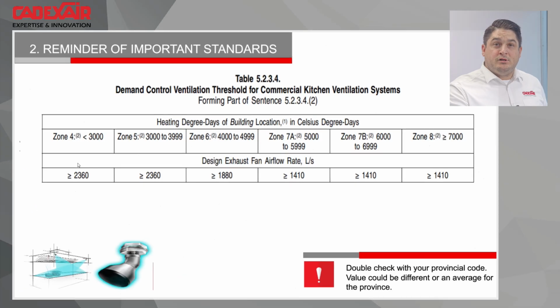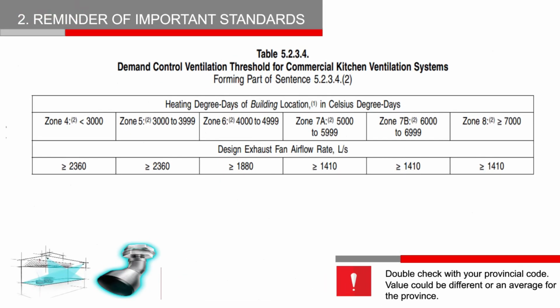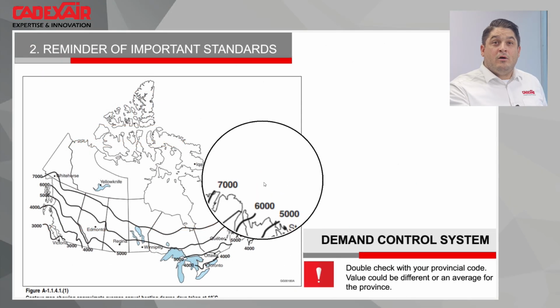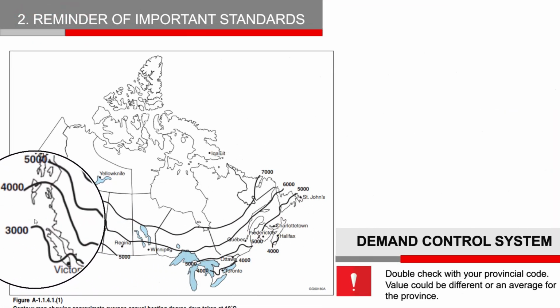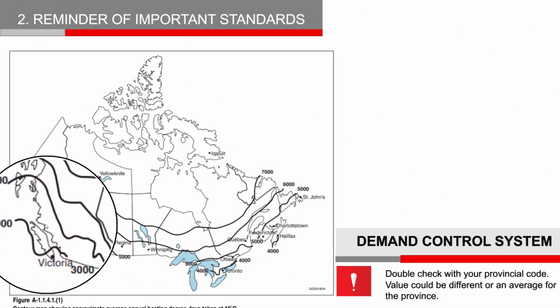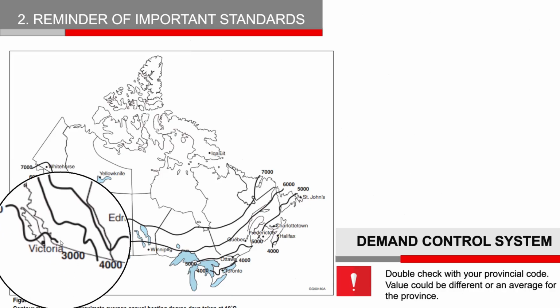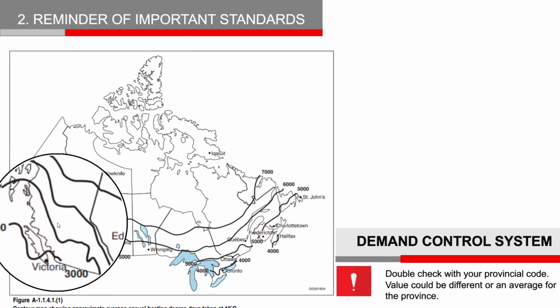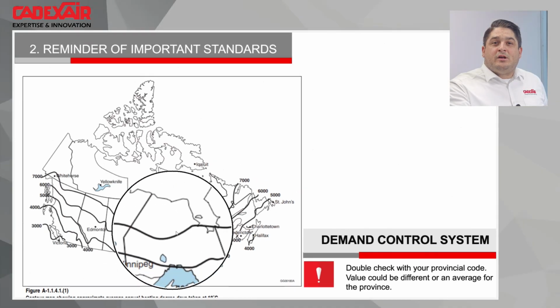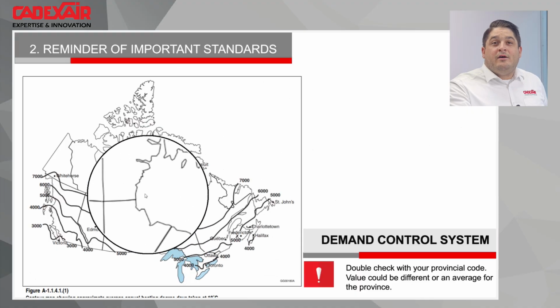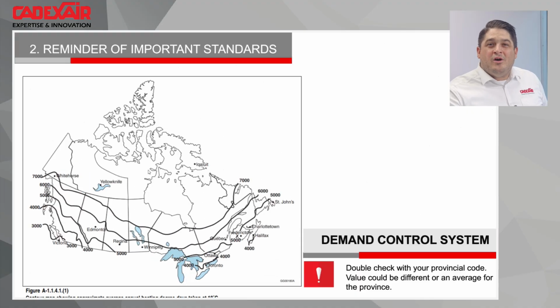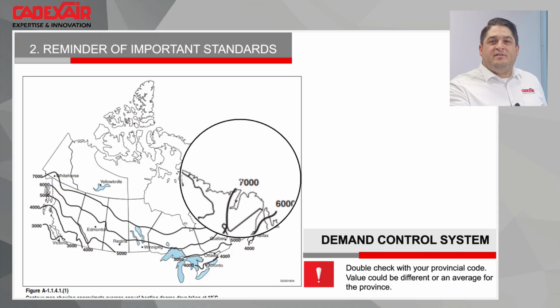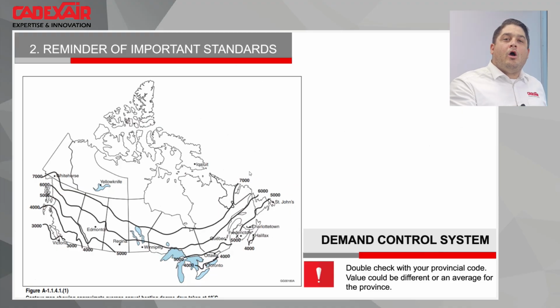So if we go back to the table, you can see, say, zone 5, 3,000 to 3,999. If we go back here, we will be somewhere between 3,000 and 4,000. So all the zone right here over Victoria will be in that zone. You have a split for everywhere around Canada, and surprise, surprise, the further north you are, the higher the value of the degree days, linked to a lower CFM to require demand control.